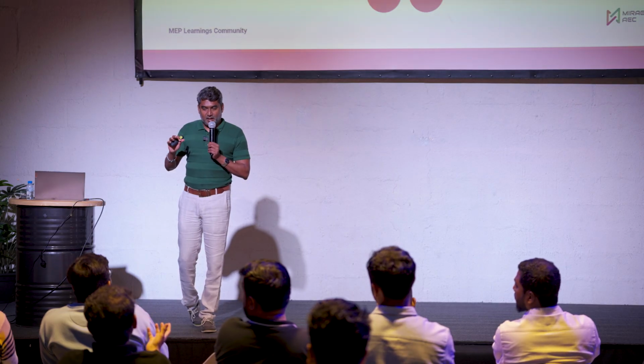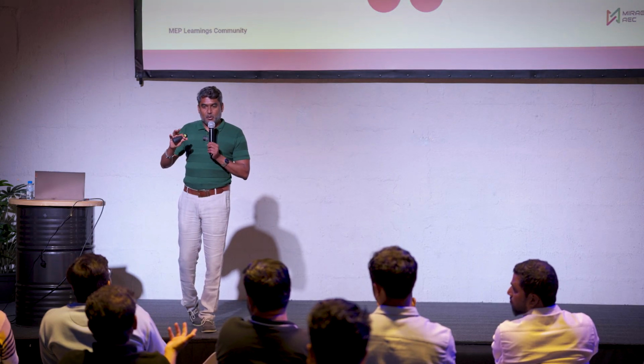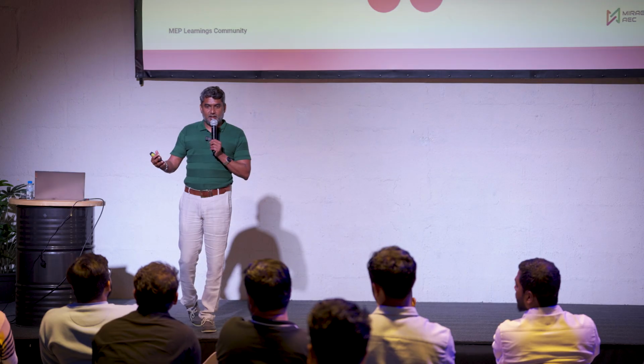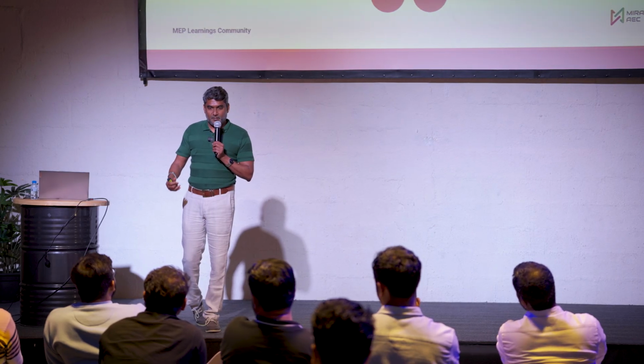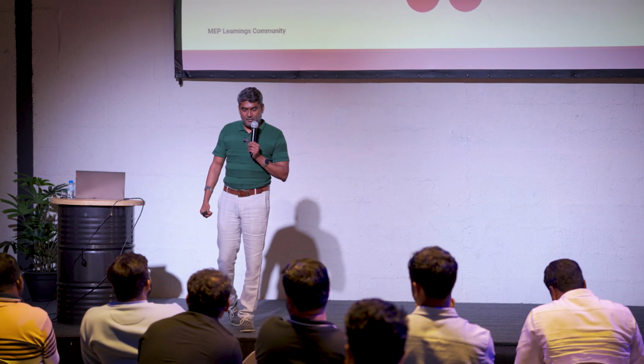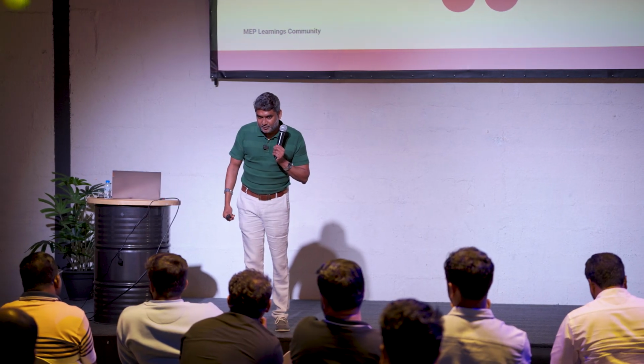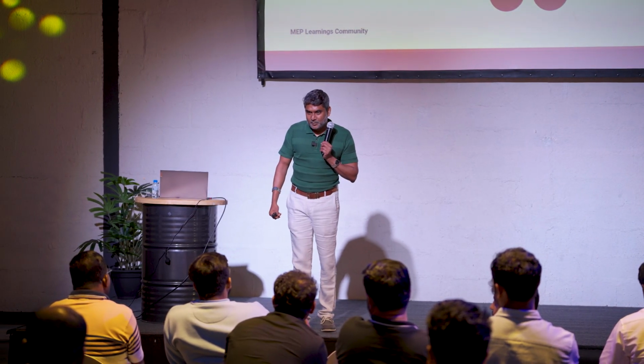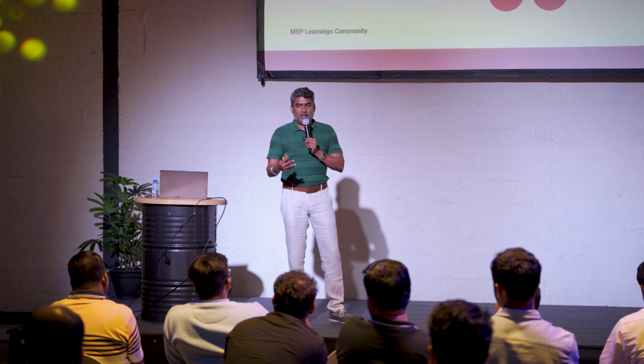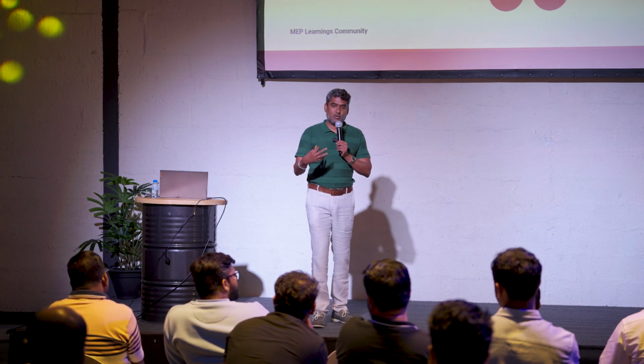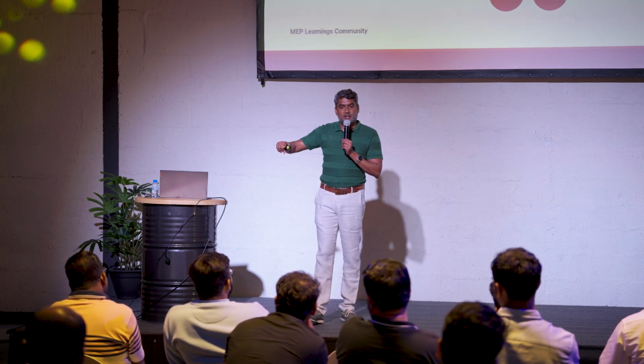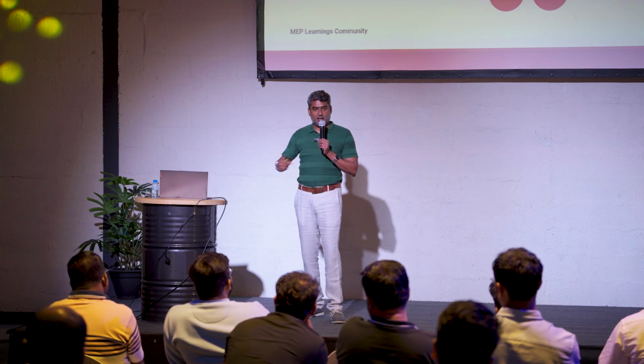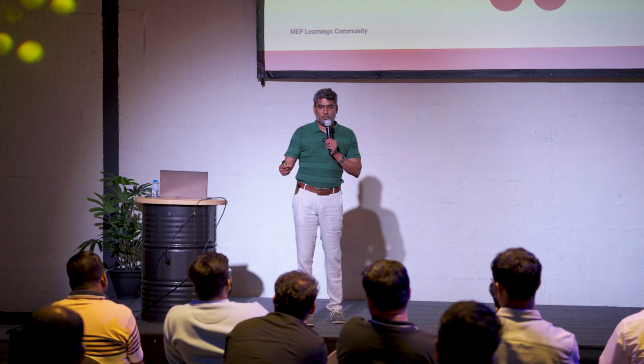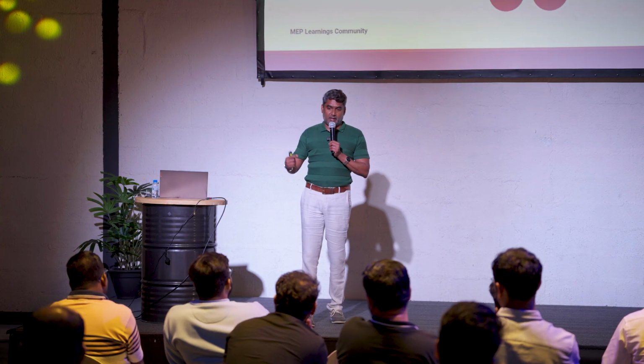Pressure sensor, right? Yes. How do you think the VFD gets the signal to ramp up or ramp down? Are we doing that interface with the VFD? Yes, the VFD has to get the signal. So that signal actually goes from BMS. The pressure sensor talks to the BMS controller, and the controller sends the signal to the VFD to ramp up and ramp down.